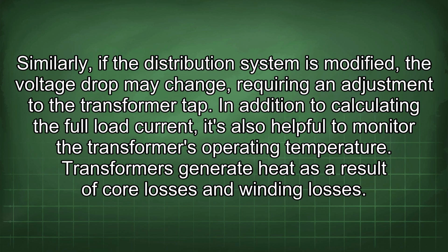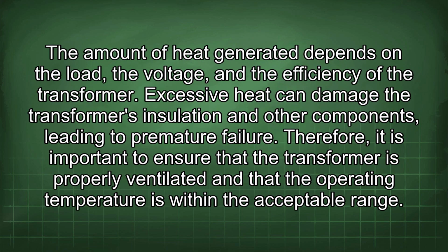the transformer tap. In addition to calculating the full load current, it's also helpful to monitor the transformer's operating temperature. Transformers generate heat as a result of core losses and winding losses. The amount of heat generated depends on the load, the voltage, and the efficiency of the transformer. Excessive heat can damage the transformer's insulation and other components, leading to premature failure.